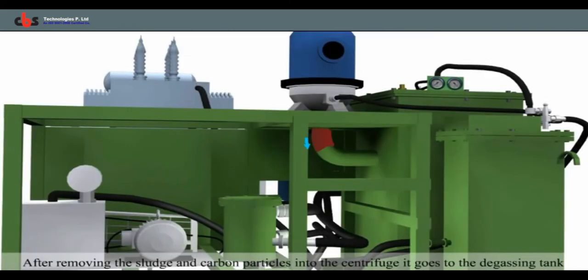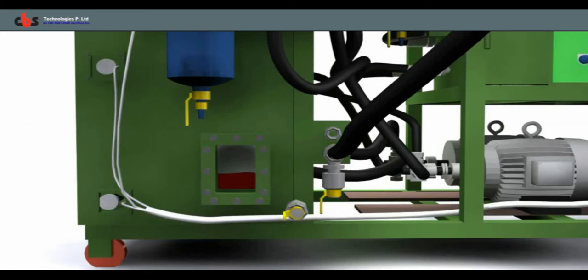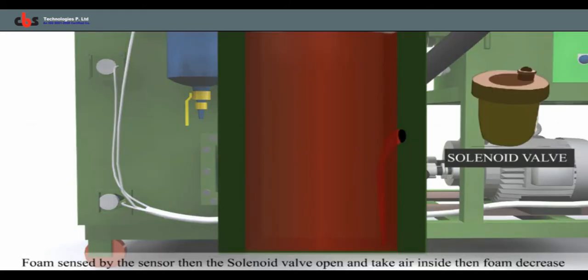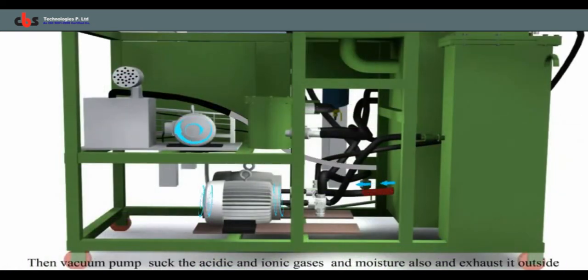Some foam is generated during this. When the foam increases, the sensor senses the foam and opens the solenoid valve attached with moisture trapper, that lets the air enter into the degassing chamber which minimizes the foam. The vacuum pump sucks the acidic and ionic gases and removes it through exhaust.